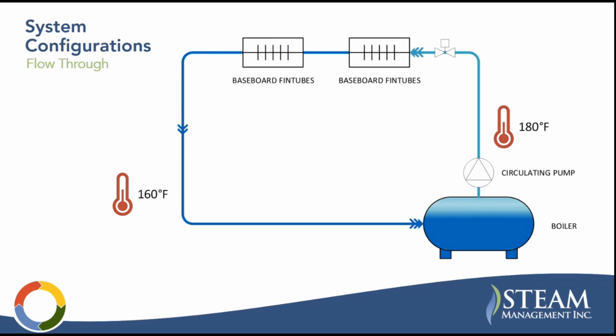This is actually a pretty good scenario for a condensing boiler because you are minimizing that return water temperature coming back to the boiler. But this is not very common for any applications that have different zones. You're going to see this in small residential applications, or maybe if it's a big storage room like a warehouse or something like that. But if you have any sort of zoning or zone requirements, this is not going to be a good application.